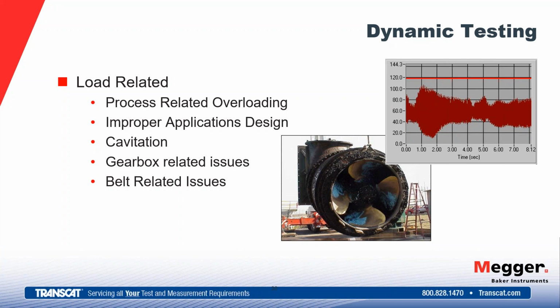Can I test my motors from the switchgear through the cables? We get asked that a lot. A lot of times it's easier to get into the switchgear than it is to break the leads at the junction box. So yes, this kind of testing can be done from the switchgear. Now not only am I evaluating the motor, but I'm also evaluating my cables and the connections in the junction box to that motor. So you're evaluating more of that system than just the motor. A lot of times there are issues that aren't just motor related. It may be that I have cables running through groundwater and that's causing issues with the motor. It's not that the motor's bad, it's that the power being delivered to that motor has issues.